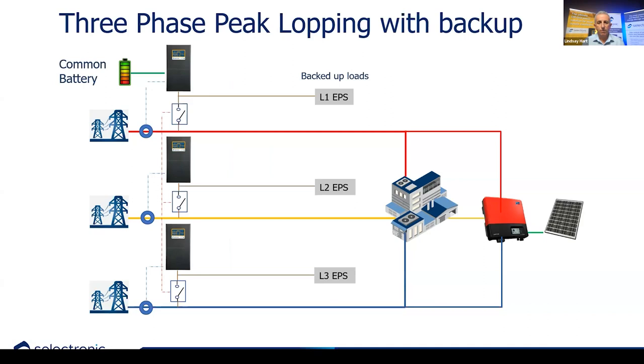And in this situation, we would be running to the capacity of the inverter. So if you've got 20 kilowatt inverters on each phase, then we've got a 20 kilowatt potential battery backup into those loads. So the size of the load is going to be determining how long the grid is off for, or perhaps how long we have to sustain more than the 100 kilowatt draw from the grid? And that will determine the size of the battery bank. So we've got to look at the frequency of the peaking events or the grid outages and the duration of them, and then we can establish the size of the battery bank and the size of the inverters.